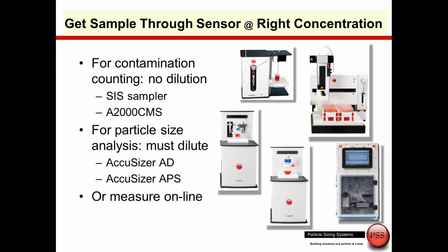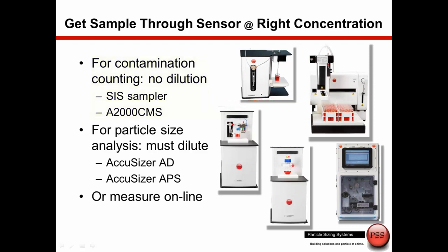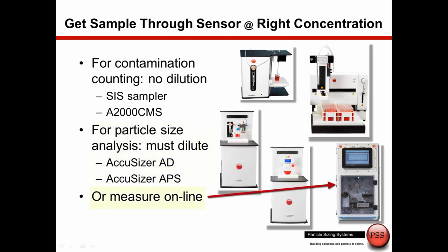To get the sample through the sensor, we use various sampler fluidics. For low-concentration samples used as a liquid particle counter without needing dilution, we could use the SIS syringe sampler or the automated AccuSizer A2000, which samples many samples and looks at contamination in hydraulic or lube oils. For higher-concentration suspensions, we have systems with different fluidics for automatic dilution: the AccuSizer AD for single-stage exponential dilution, and the AccuSizer APS for dual-stage dilution. We also have online systems for any of these measurements in a process environment.